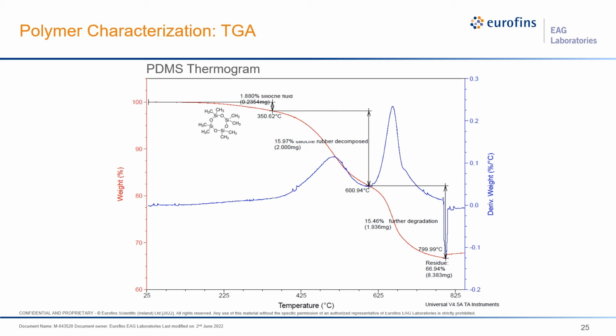As the sample heats up under nitrogen, small volatile components can evaporate or volatilize, and this is observed as a mass loss. As you reach higher temperatures, you can start to degrade and decompose the polymer, and again, you can observe this as a mass loss event. Looking at this sample, we see it contains about 2% of volatile to semi-volatile materials up until about 350 degrees. This could include small cyclic siloxanes like the D4 that's shown in the spectrum. Next, we see two larger thermal decomposition events of about 15% each. This is actually the PDMS backbone breaking down into smaller fragments, volatilizing and leaving the sample pan. The most important piece of information that we'll take away from this is that after heating the sample to 800 degrees C, 67% of the initial sample mass still remains on the balance.